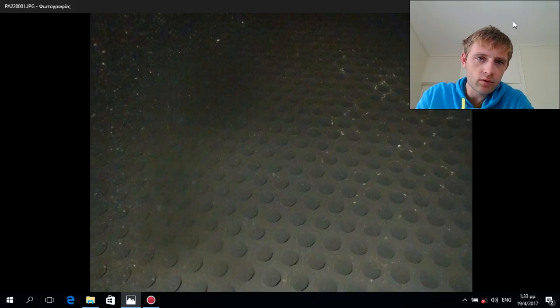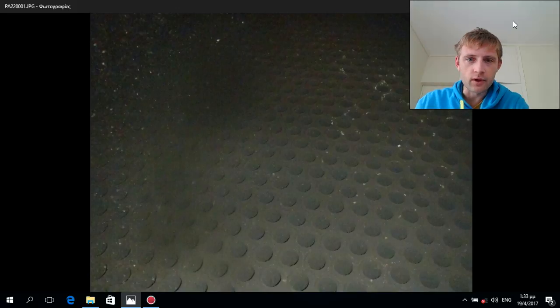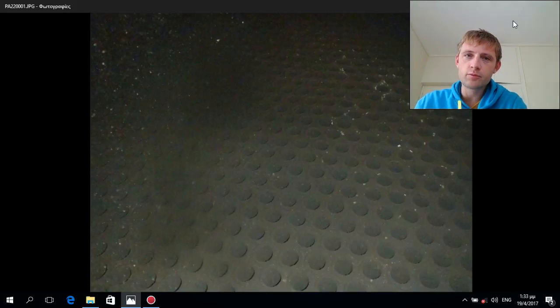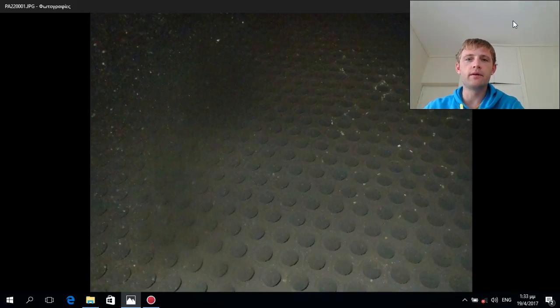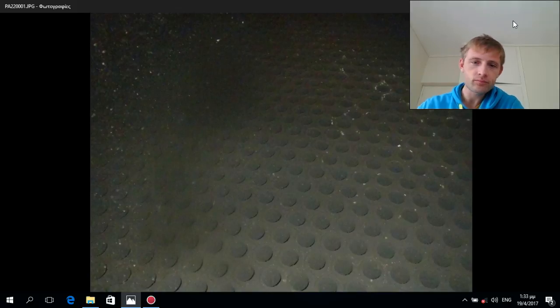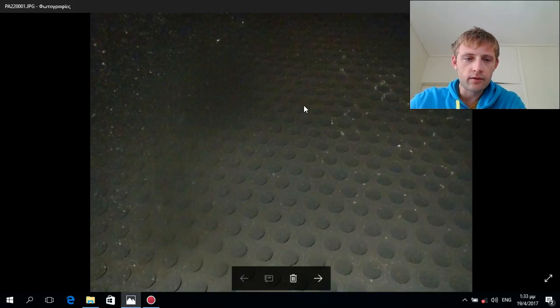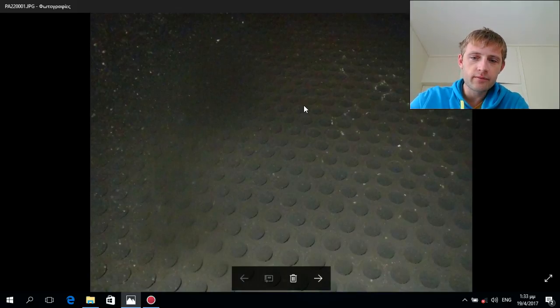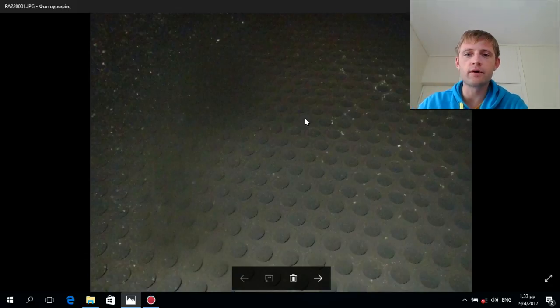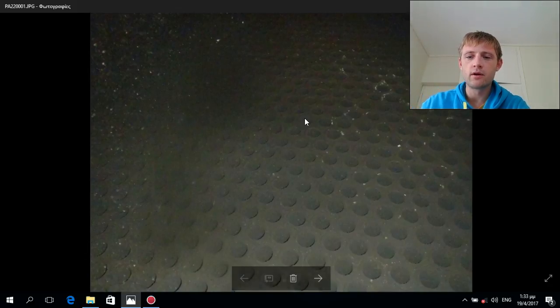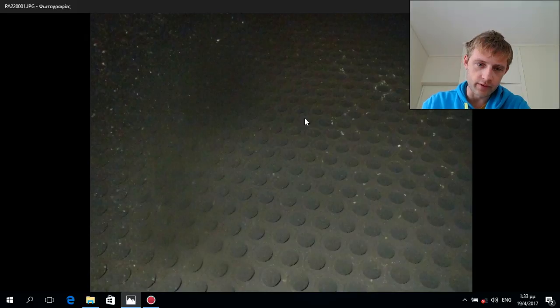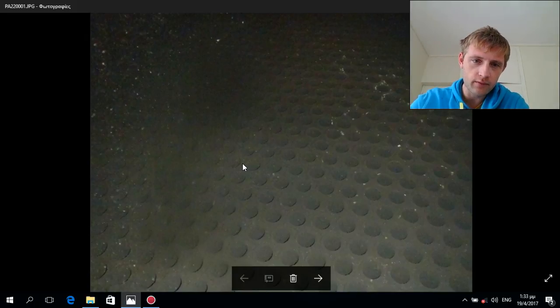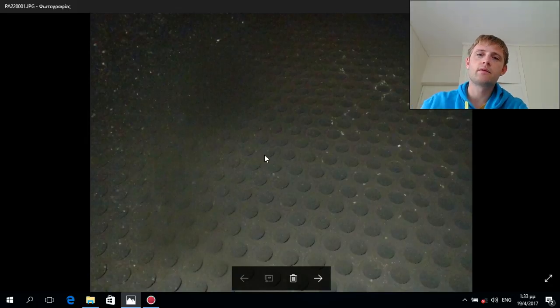Today I have this beautiful video for exhaust gas economizer. These are the tubes as you can see when you open the inspection door. They're a little bit dirty, it's not so much, but this kind of exhaust gas economizers are the best because the tubes are quite big enough.